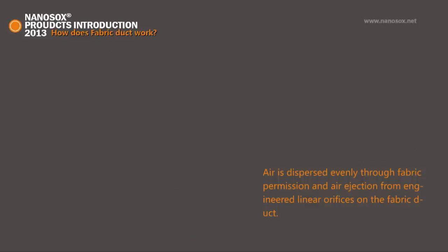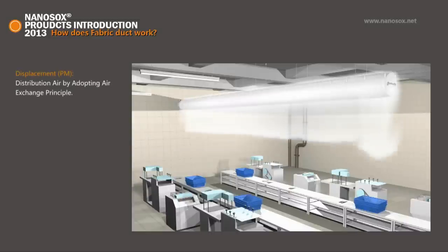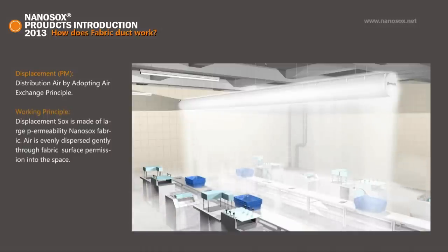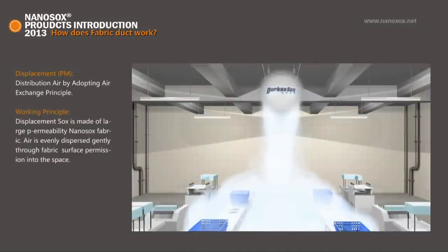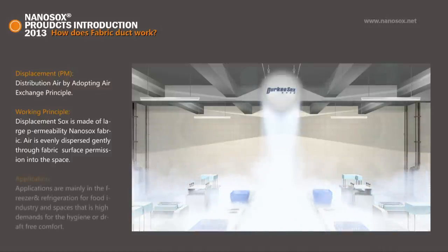There are four kinds of airflow models. Displacement PM: Displacement Sox is made of large permeability Nanosox fabric. Air is evenly dispersed gently through fabric surface permeation into the space. Applications are mainly in the freezer and refrigeration for the food industry and spaces with high demands for hygiene and draft-free comfort.